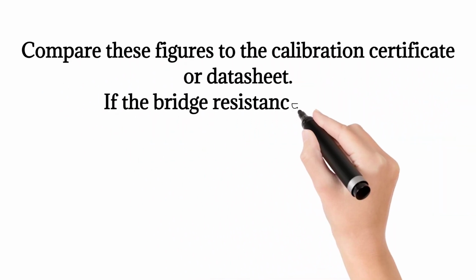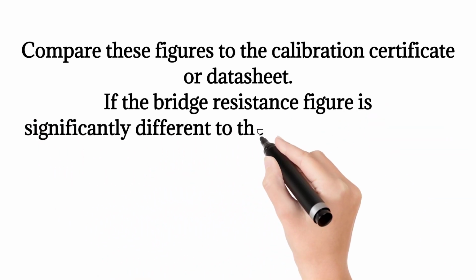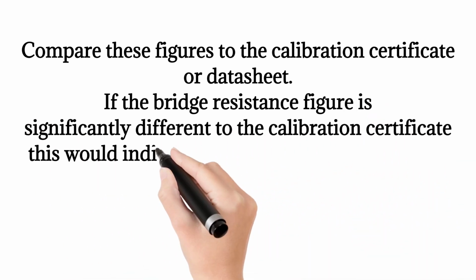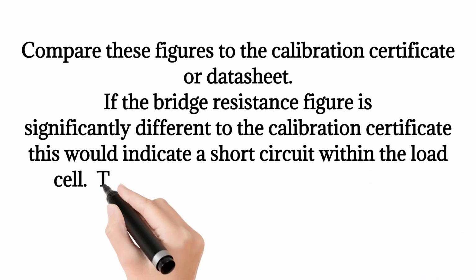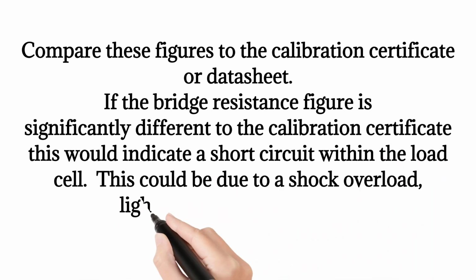If the bridge resistance figure is significantly different to the calibration certificate, this would indicate a short circuit within the load cell. This could be due to a shock overload, lightning or electrical surge.